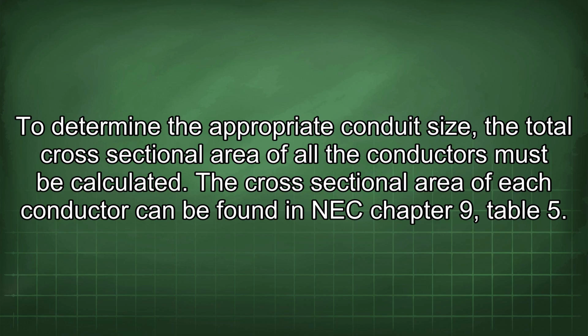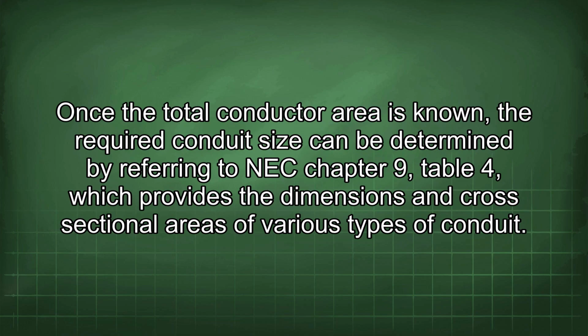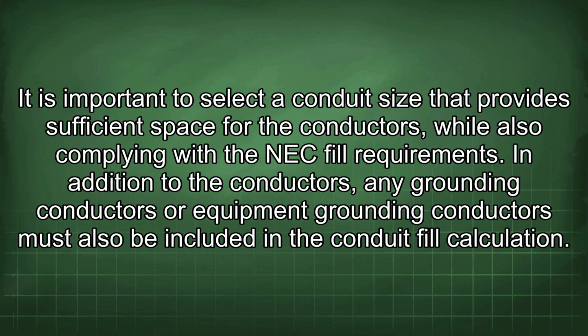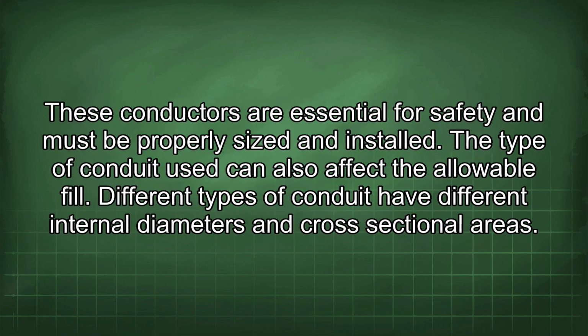The cross-sectional area of each conductor can be found in NEC Chapter 9, Table 5. Once the total conductor area is known, the required conduit size can be determined by referring to NEC Chapter 9, Table 4, which provides the dimensions and cross-sectional areas of various types of conduit. It is important to select a conduit size that provides sufficient space for the conductors, while also complying with the NEC fill requirements. In addition to the conductors, any grounding conductors or equipment grounding conductors must also be included in the conduit fill calculation. These conductors are essential for safety and must be properly sized and installed.